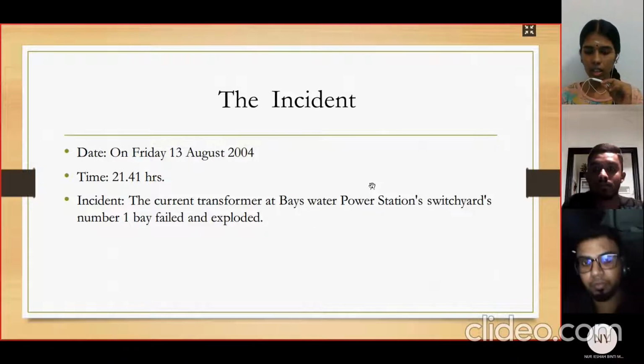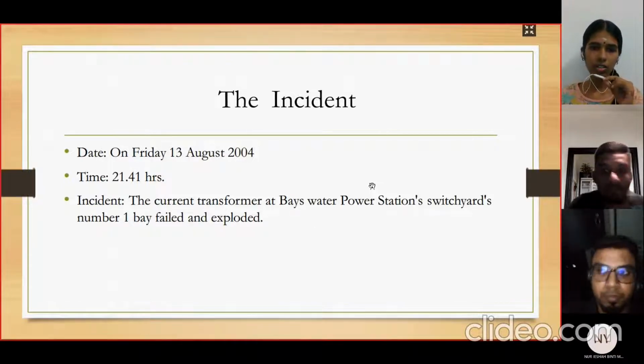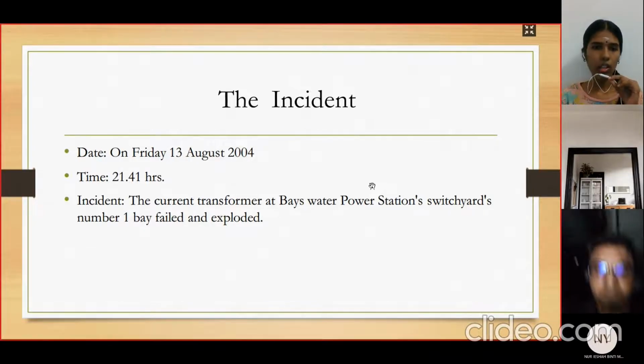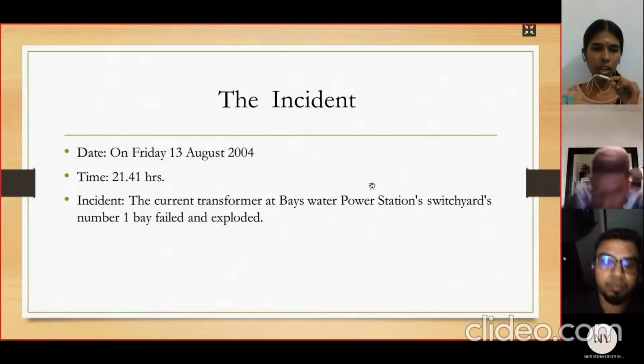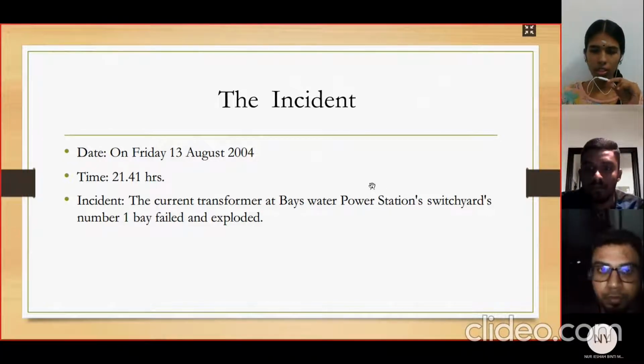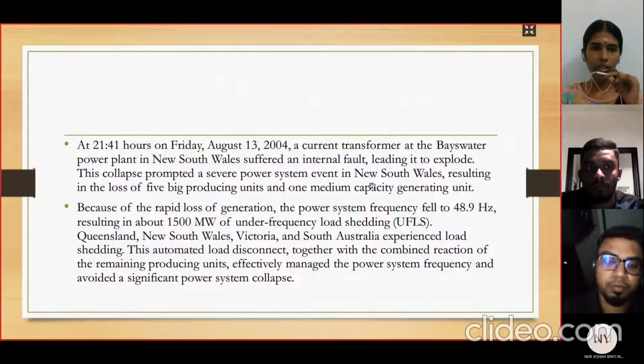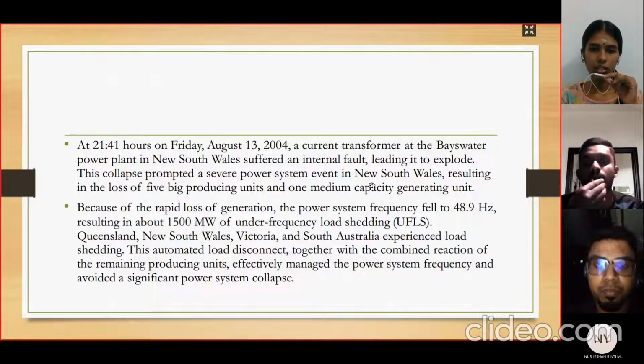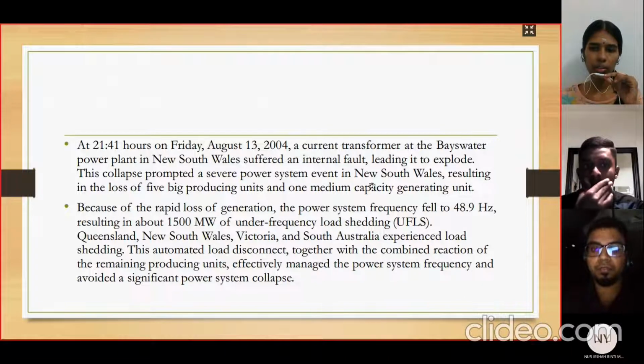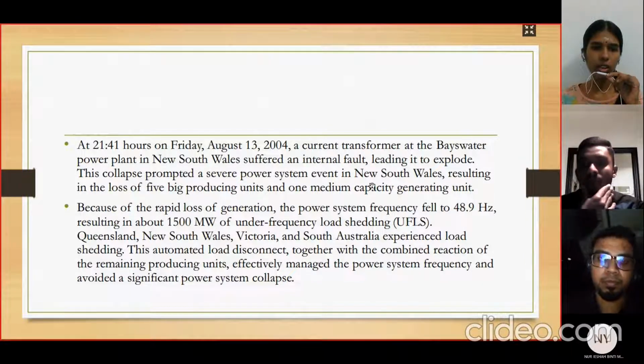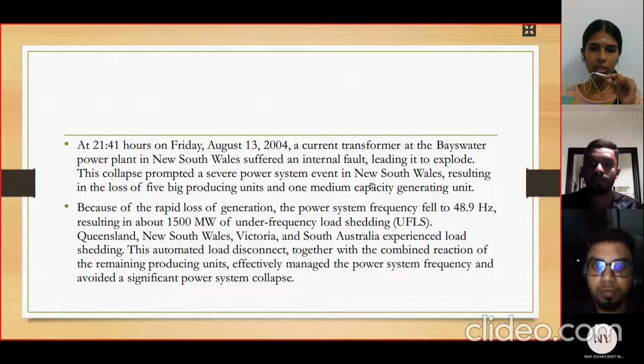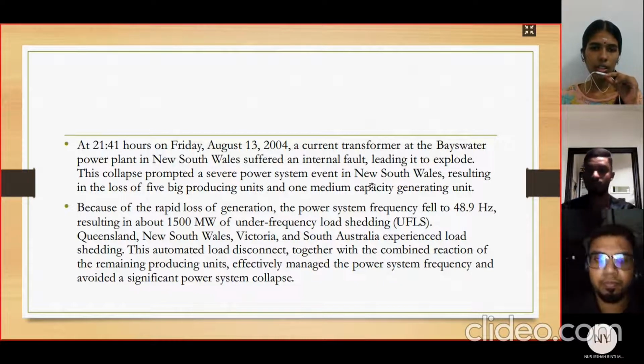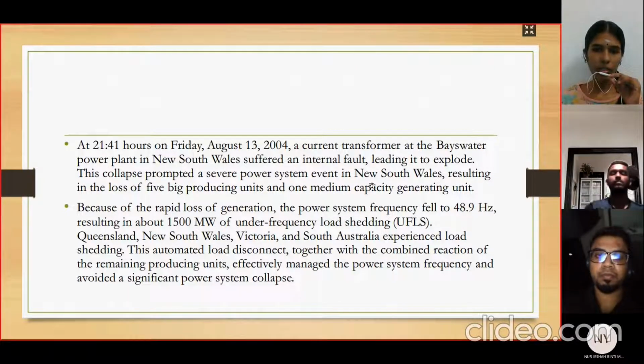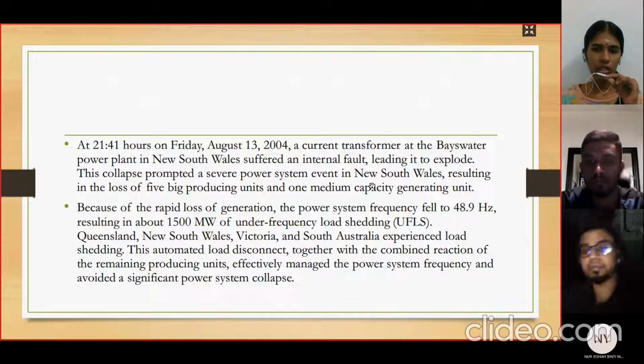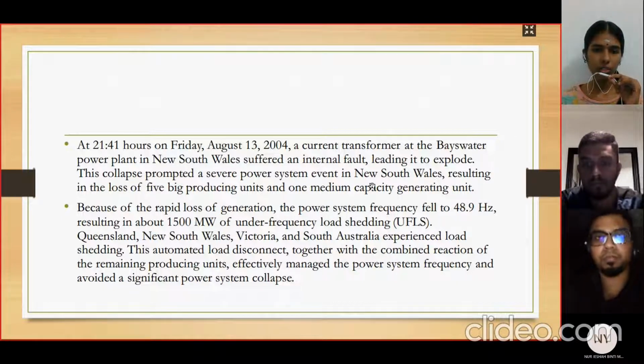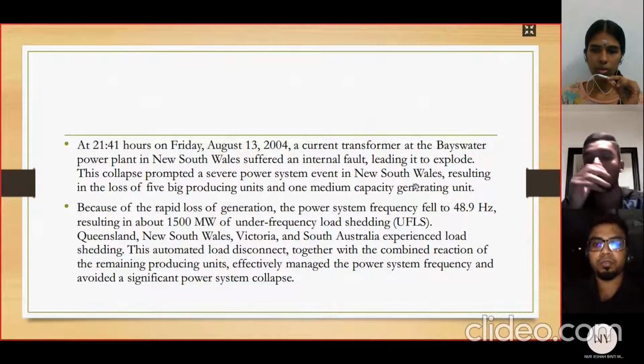First, the incident happened on Friday, 13 August 2004, at 9:41 p.m. A current transformer at the Bayswater Power Plant in New South Wales suffered an internal fault, leading it to explode. This collapse prompted a surge in the power system in New South Wales, resulting in the loss of 5 big producing units and 1 medium capacity generating unit.